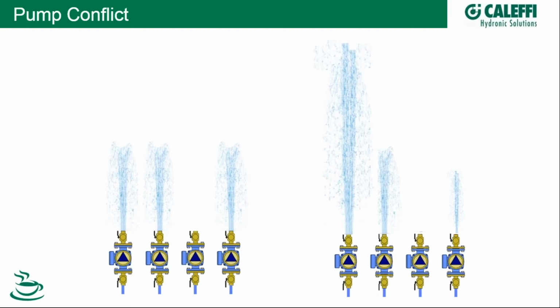and the circuit, or the items in that circuit, may not work correctly. Mind you, they have more flow than their design flow, at least for that application, and they might not even work properly. So those are issues with overflow. Underflow, well, this seems like it might be obvious. With underflow, you're not getting the heat transfer that you want that circuit to accomplish. So that's a problem with pump conflict.